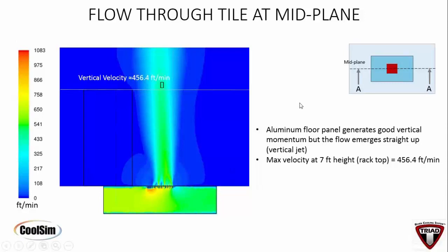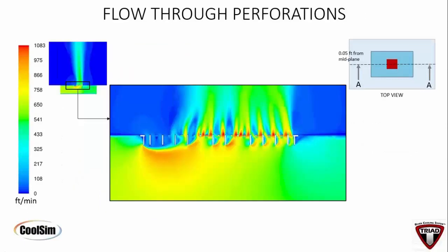In other words, high velocity is not perfect. It's not always good. You need enough velocity, but here under the same conditions, by the way, our fan's having to run harder and we're dumping more air. So this is under high energy consumption situations, you're getting this big jet.